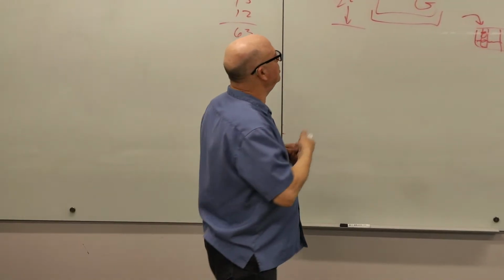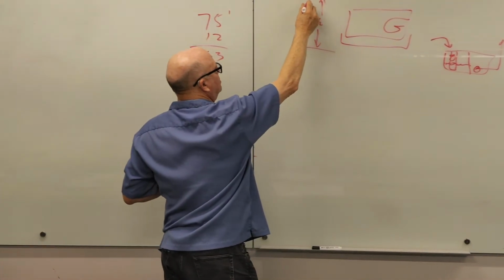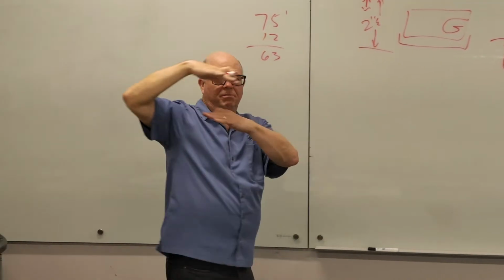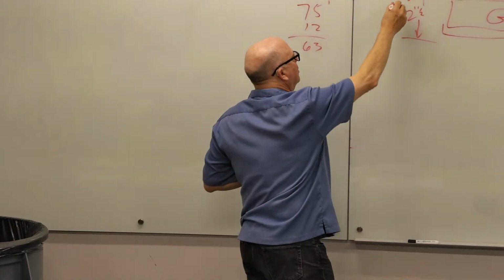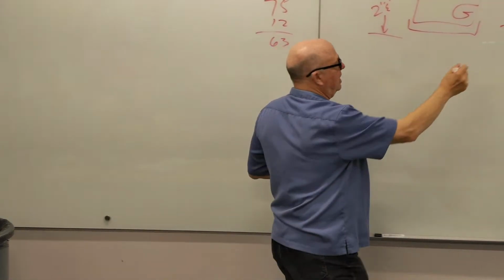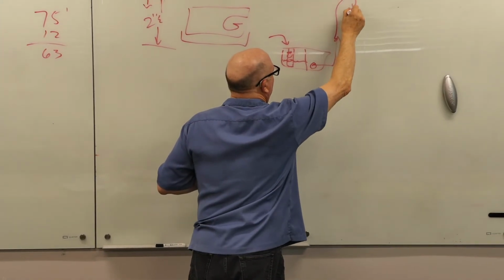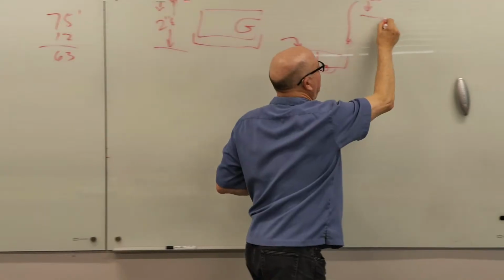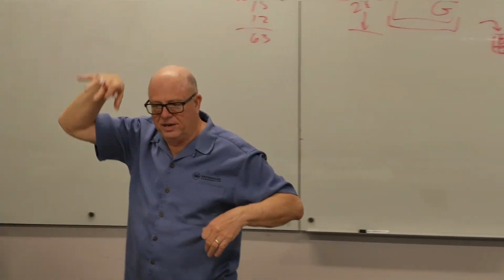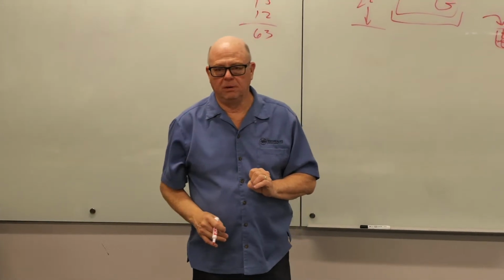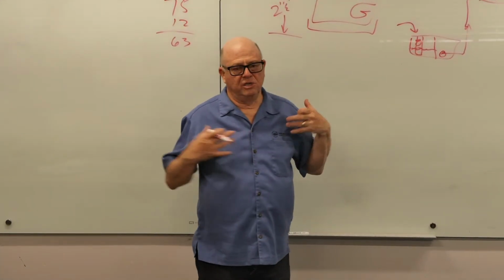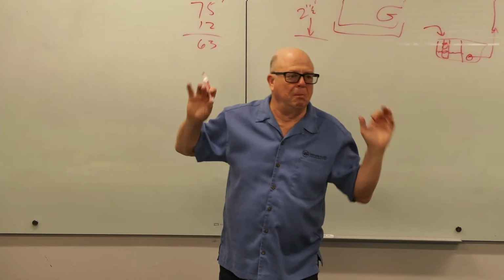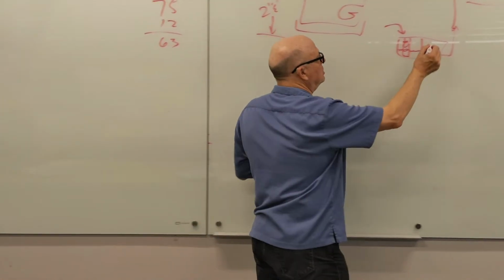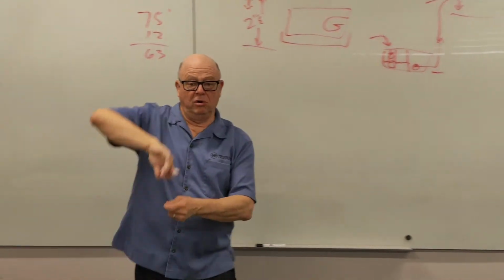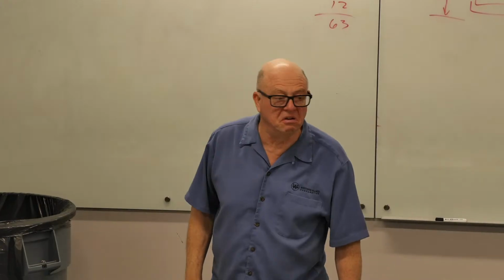And typically what you'll do is you'll be hanging it maybe this high off the ceiling with a little spout that goes up. And you'll run maybe some 3/8 soft copper around into the top of the condensate line that's running high. And that gives it the fall. That's usually what you do. Now, when you're buying a condensate pump, unless it was a really big unit, I wouldn't worry about how many GPM it'll pump. But the relevant thing is, how much head will it overcome? In this application, you're only bumping it up a couple of feet. It's not a big deal.